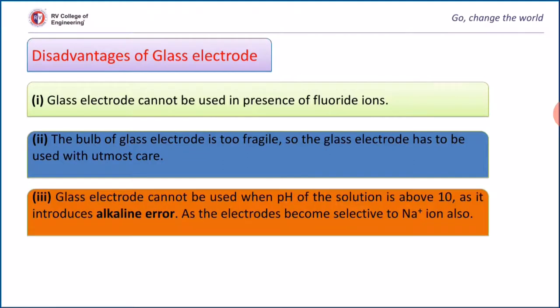Third, glass electrode cannot be used when the pH of solution is above 10 as it introduces alkaline error. The electrode becomes selective toward Na+ ions also, which results in wrong results. Hence, we should avoid pH more than 10.